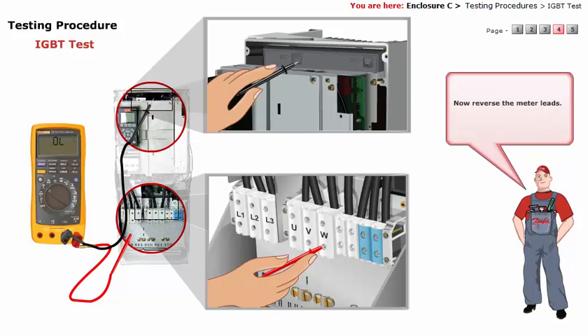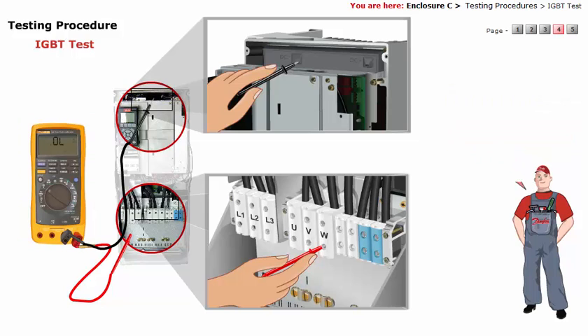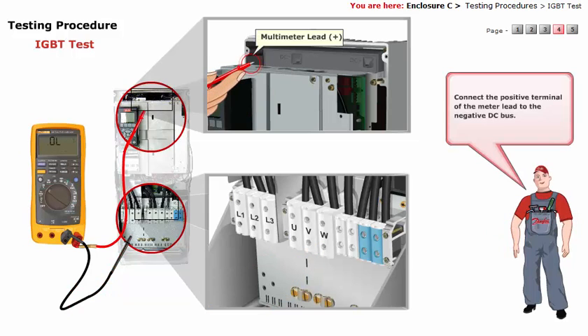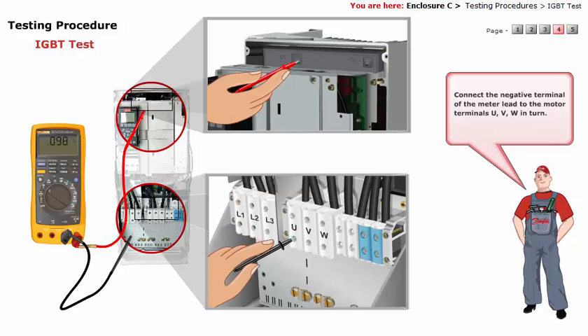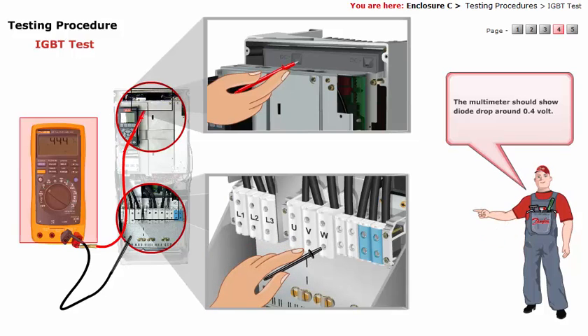Now, reverse the meter leads. That is, connect the positive terminal of the meter lead to the negative DC bus. Connect the negative terminal of the meter lead to the motor terminals U, V, W in turn. The multimeter should show a diode drop of around 0.4 volt.